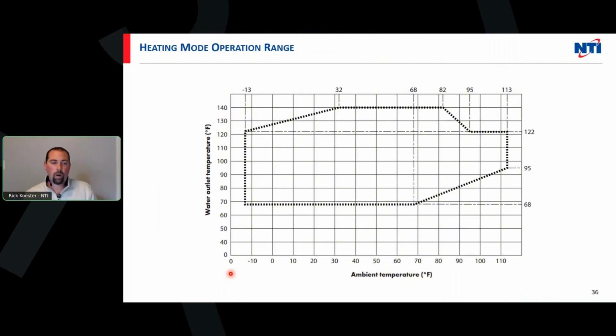When we're designing a system around water temps, this is a cool chart that I've never seen in any other manufacturer's IO manuals. I was really pleased to see this, because if I was designing a system using a specific type of heat emitter where I knew I had to get a certain amount of BTUs out of it, I needed to have X water temp. I can come in here now and get an idea that, from 100 and looks like about 123 degrees, we'll call it 121 degrees. Actually, it's 122. It's right there. I don't have to guess.